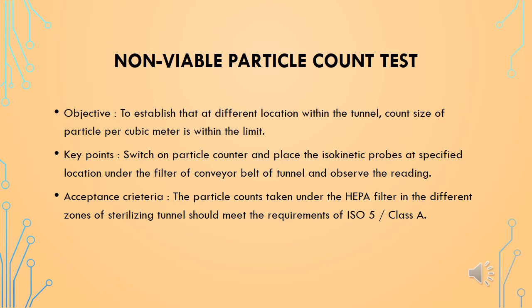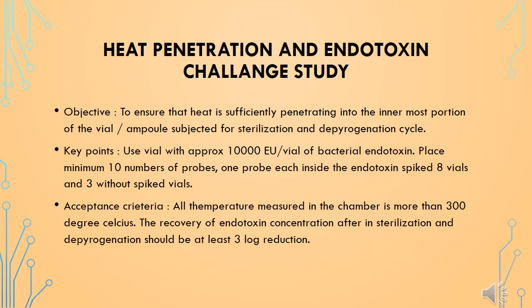Particle counts for all the zones of the sterilizing tunnel shall be taken into consideration. The acceptance criteria for non-viable particle count is that the particle counts taken under the HEPA filter in the different zones of the sterilizing tunnel should meet the requirements of ISO 5 or Class A.